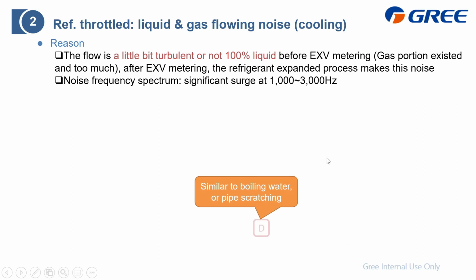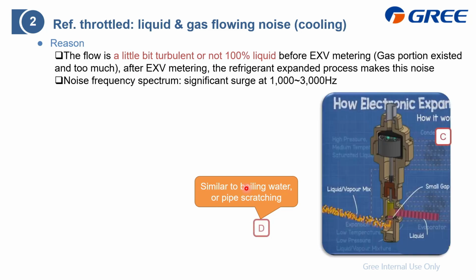Okay. And also you can find that this noise is just similar to boiling water, or the inside water or liquid just scratching the pipe, right? Here I'd like to explain why and how this noise comes out. As you know, for the VRF system in cooling mode, the refrigerant is metered at the indoor unit EXV, and before that it should be completely liquid. Then when it gets metered, it becomes liquid and vapor, which is a refrigerant gas and liquid mixture. Then it goes to the indoor heat exchanger to do heat exchange, which is cooling.